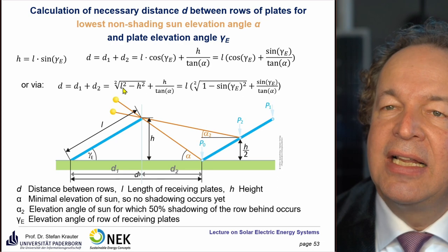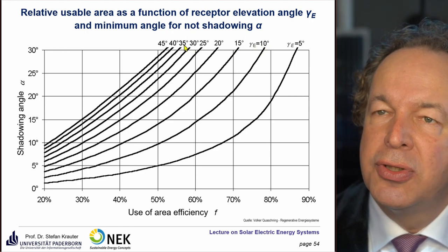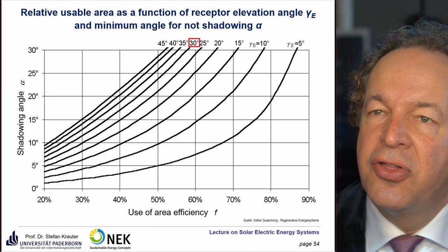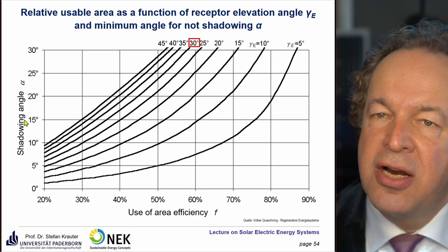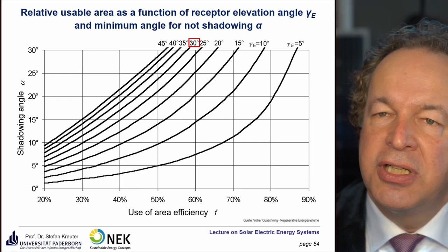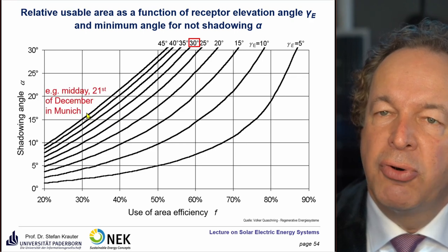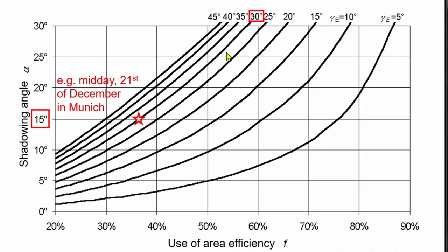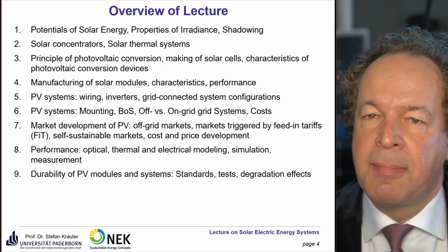For an optimal energy yield in central Europe, a module elevation angle of about 30 degrees is recommended. The shadowing angle — the sun's actual elevation angle on the 21st of December at midday — is approximately 14 to 15 degrees, for example 15 degrees in Munich. Combining these two values leads to a land use area of about 36%.